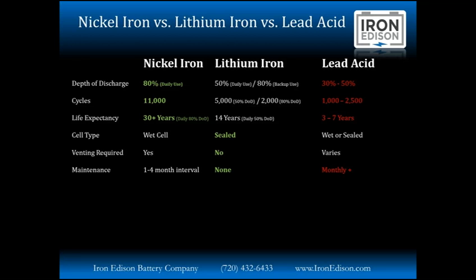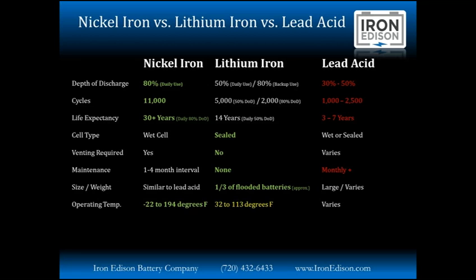Venting varies as well, and maintenance: if it's a flooded lead acid, you're doing maintenance at least monthly, if not every couple weeks. As far as size and weight, nickel iron batteries are similar to lead acid, but their operating temperature range is probably the greatest of any battery chemistry out there. Nickel iron batteries can operate from 22 below Fahrenheit up to 194 degrees Fahrenheit with no real noticeable performance changes.